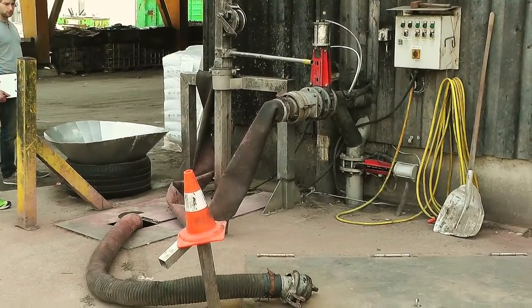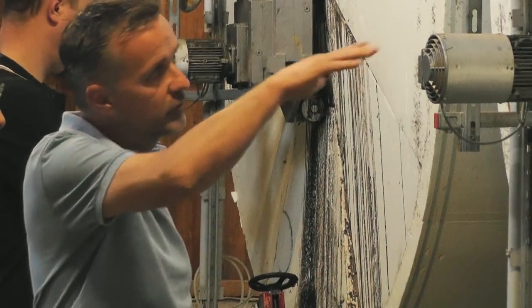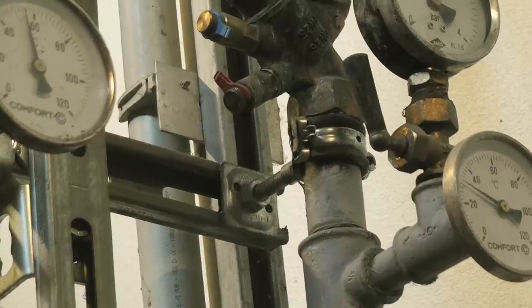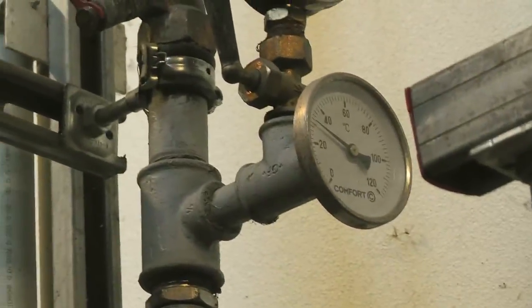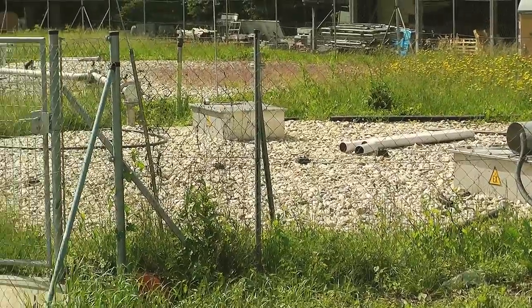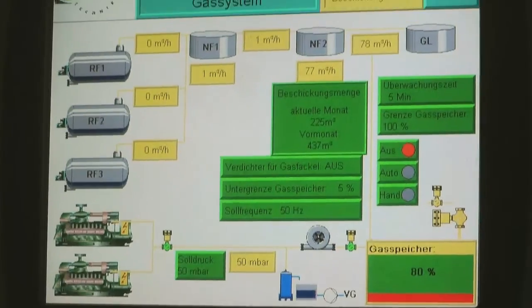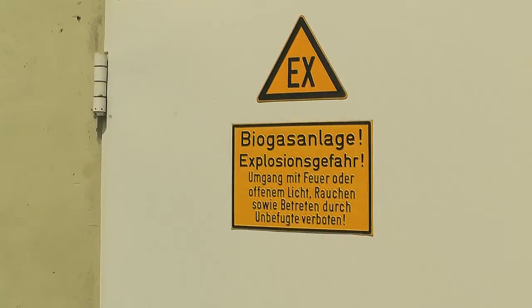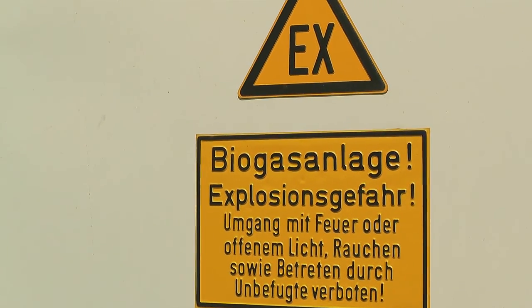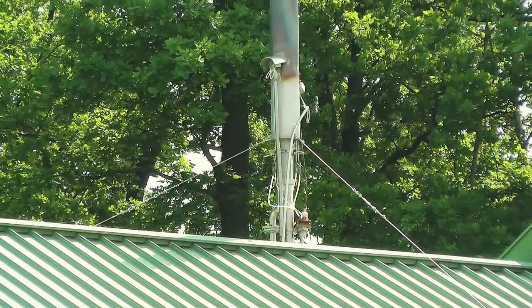After that the food waste is put into the fermenter with a total capacity of 680 cubic meters, where about 78 cubic meters of biogas per hour with 60 to 65 percent methane are produced. As temporary storage, a gas bag is used to store about 200 cubic meters of biogas.